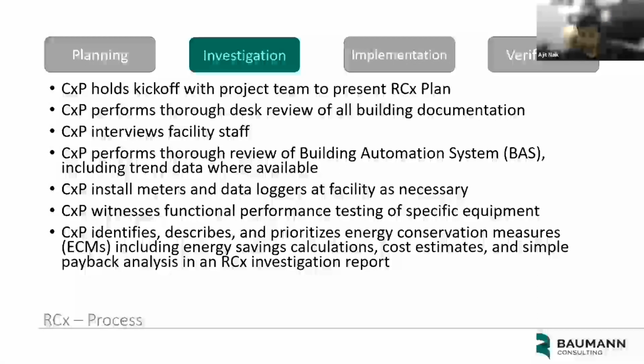Next, we move on to investigation. The commissioning provider really takes over at this point. The commissioning provider holds a kickoff meeting with the project team to present the plan. They perform a thorough desk review of all building documentation: equipment lists, nameplate photos, drawings, as-builts, previous commissioning reports, energy studies, anything at all. We'll take it and we'll review it. We interview facility staff to ask them questions about comfort, how the building operates, and its history. We perform a thorough review, where available, of the building automation system, the computerized system that controls the building MEP systems. We review trend data where available. We install meters and data loggers when needed. For some specific cases, we will write scripts for functional performance testing of major energy consuming systems.